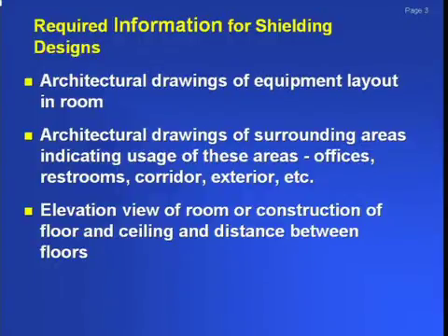We built one vault, and I was assured it was completely an exterior vault. We shielded it accordingly because they were trying to save money. Within 6 months, they built the medical office building immediately adjacent to it and put the administrator's office directly across from isocenter.